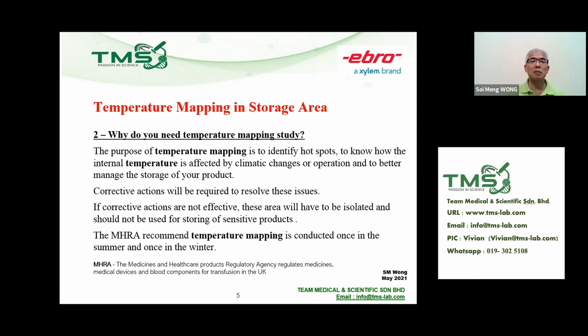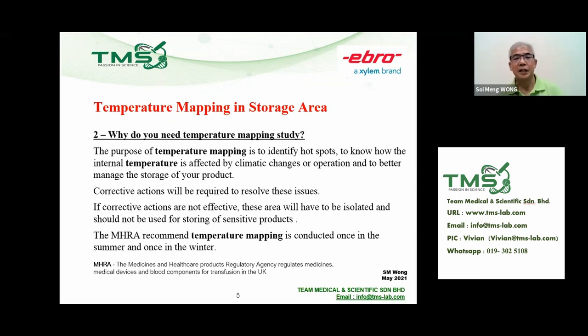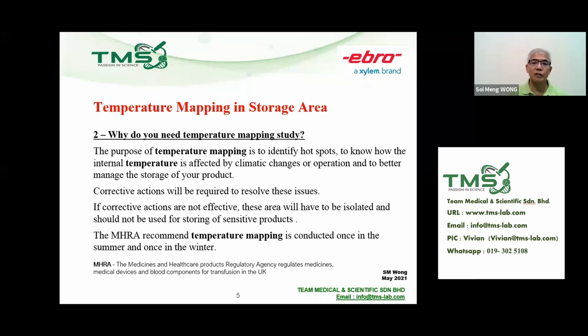Why do you need temperature mapping? The purpose is to identify hot spots, to know how internal temperature is affected by climate change or operations, and to better manage storage of your products. Corrective action should be taken to resolve issues; if corrective actions are not effective, the area should be isolated and not used for storing sensitive products. The MHRA recommends temperature mapping be conducted once in summer and once in winter — in our case, perhaps the rainy season. MHRA is the Medicine and Healthcare Product Regulatory Agency from the UK.